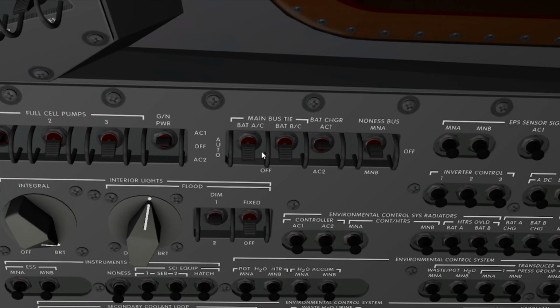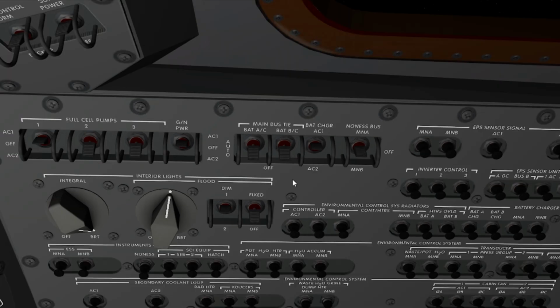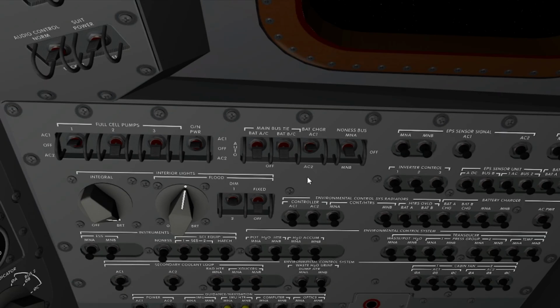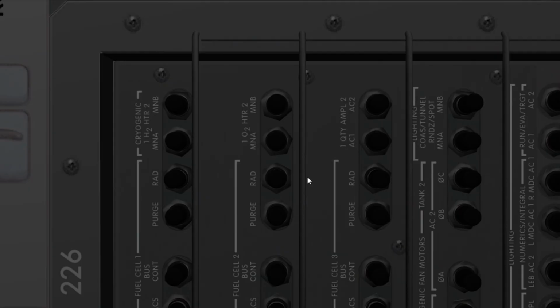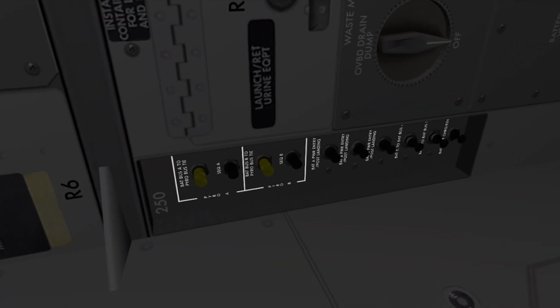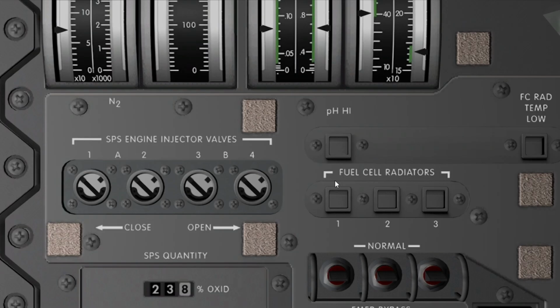Battery charger check, so making sure our main bus ties are off. We verify that bat bus A to pyro bus tie is open, bat bus B to pyro bus tie is open, bat C to bat bus A is open, and bat C to bat bus B is open.